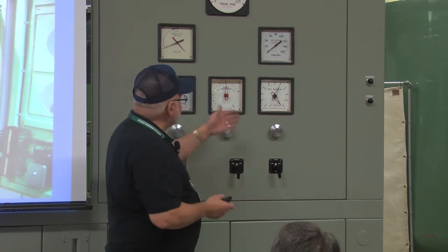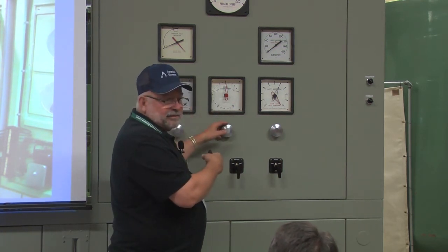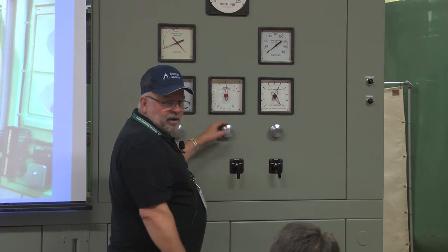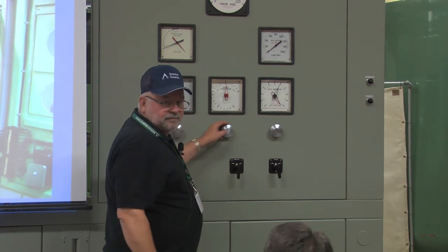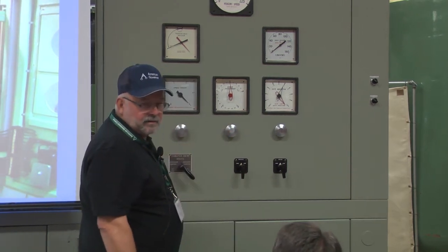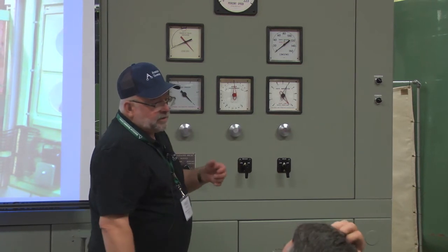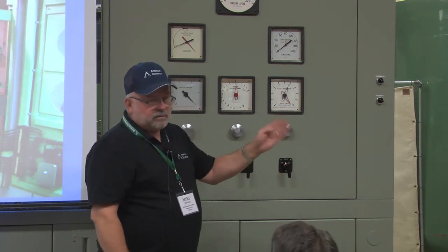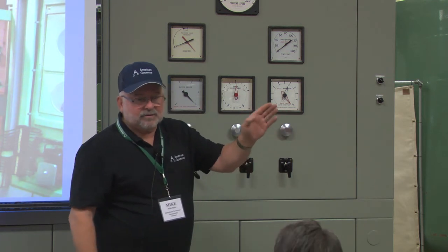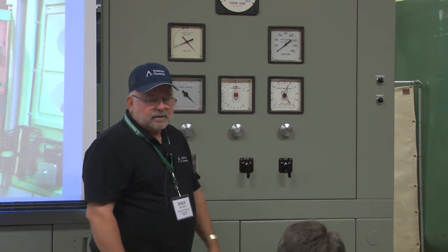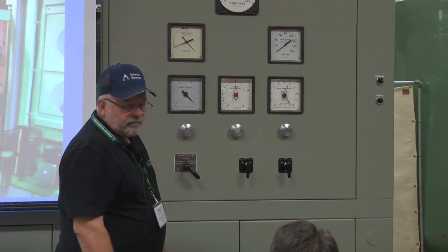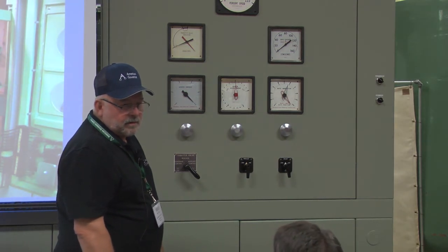That's the difference. When our machine starts up, it's to the minus. It is? Well, it's just because they probably set that to the minus. Well, it's automatic. I mean, when they run it back down, it automatically runs it back down before it disconnects. Now, when they go out to start the machine, does the operator go out and raise it up, or he just starts it and then lets the auto sync? Yep, they just hit start. Unless we got one unit that's been giving them a little trouble, they've had to go do a manual sync on it.